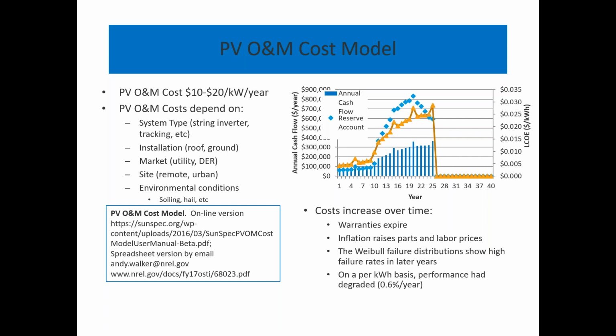The cost is actually different every year, because it's based on Weibull distributions for the Sandia measures, plus the working group's judgment on failure distributions for components we didn't have data for. The cost goes up over time because our betas are greater than 1, so we're looking at a fatigue-related profile where failure rates get higher as equipment ages and warranties expire. On a per-kilowatt-hour basis, costs go up even more because we assume plant production declines about 1% per year.